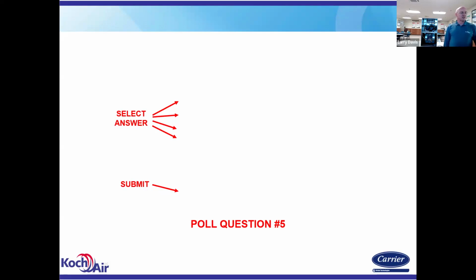All right, we're a little split on this. So about 32% of you said it's the 25 speed on the mid-tier, and about half says the 18 speed, and there was a few that went with the other options. So the entry-level tier or the base model furnaces are the 18 speed, okay? The mid-tier is a 25 speed. We have more speed options in that mid-tier, and we can fine tune that blower, especially when we're using two-stage heating and two-stage cooling. So the correct answer there is A, the 25 speed. Excellent. Moving right along.